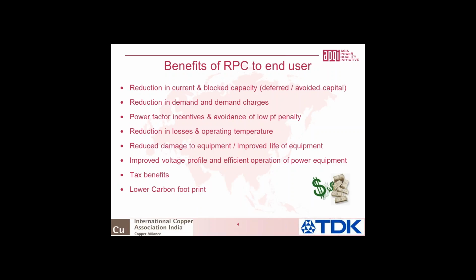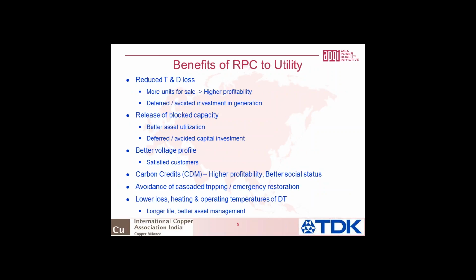Now let's look at what are the benefits for the utility. For example, if you have lower currents flowing in your T&D network and your transformers, you have a lower T&D loss. So whatever the reduction in the T&D loss, that many real units are available for sale, which means you have a higher profitability, which is the need of the hour for the Indian utilities. Also, it means deferred or avoided investment in generation. You don't need to go on adding generating capacity because whatever the watts you are saving out of T&D loss reduction is now available for sale.